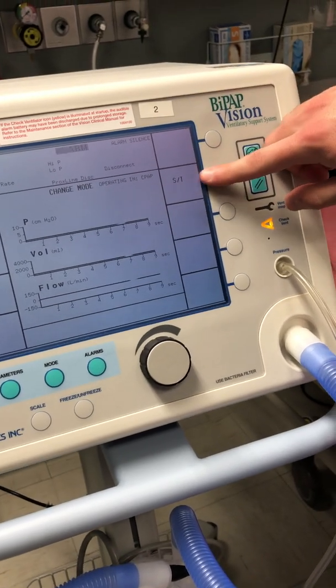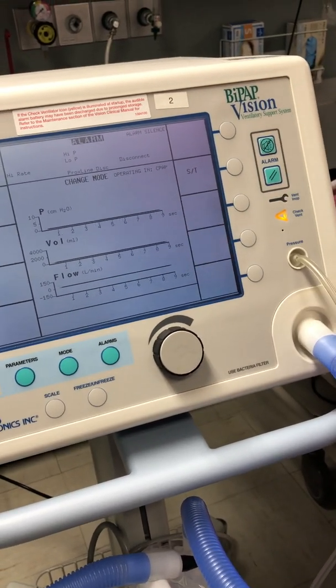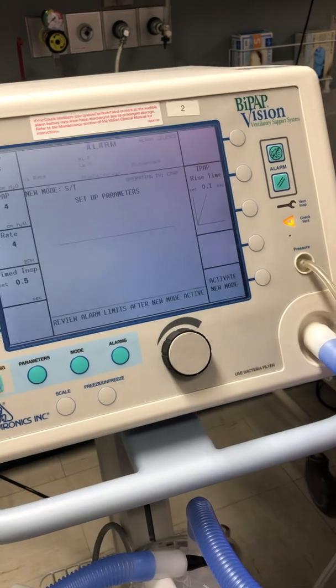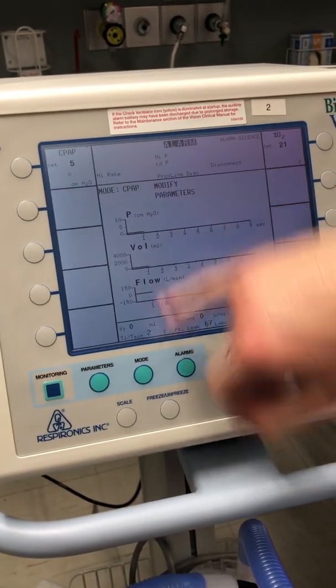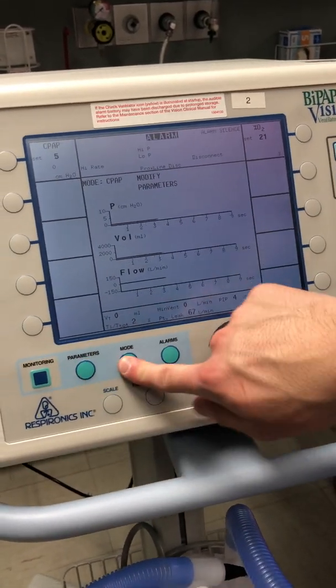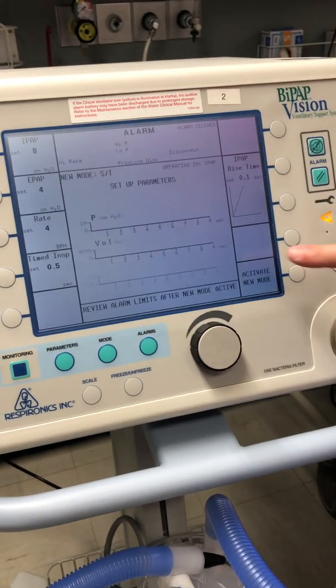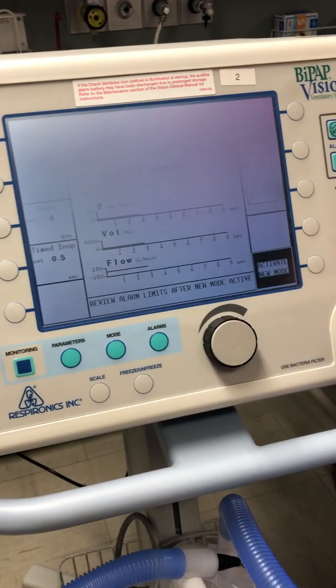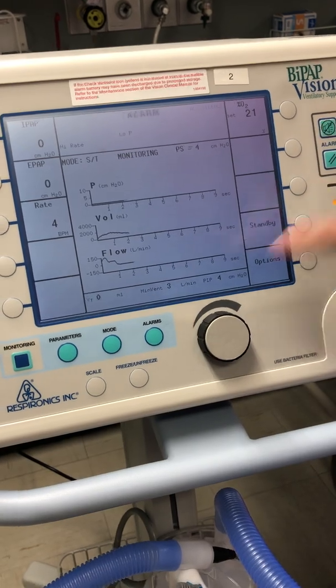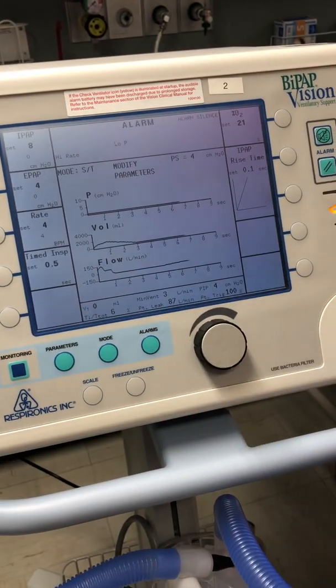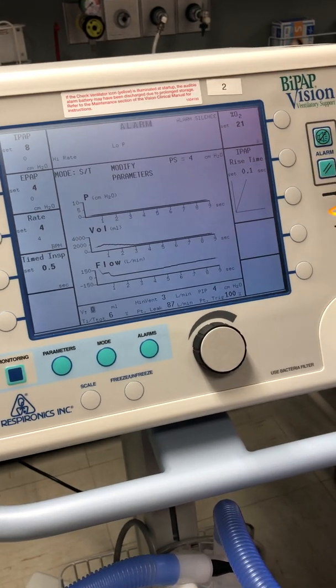There's your BiPAP. BiPAP is ST, standing for spontaneous and timed. When you press that, you can then go to parameters and also adjust. Oh, I did not confirm it, sorry. You press mode, you press this, you press activate new mode. And then you go into the parameters and you can set your EPAP, your rate, your inspiratory time, and then your ramp and all that stuff.